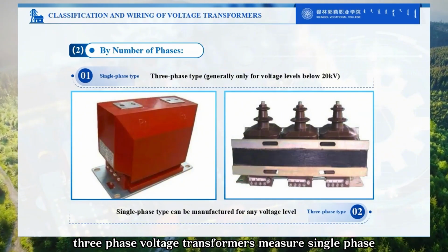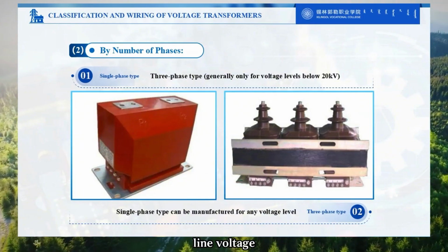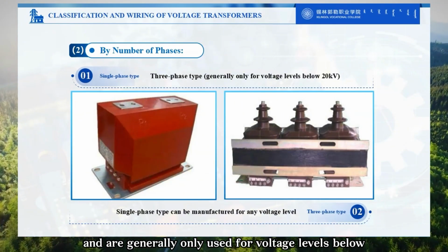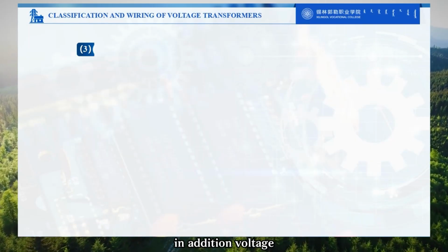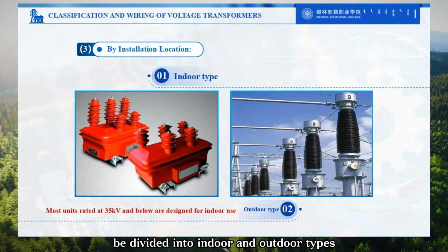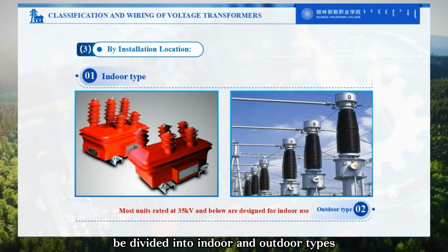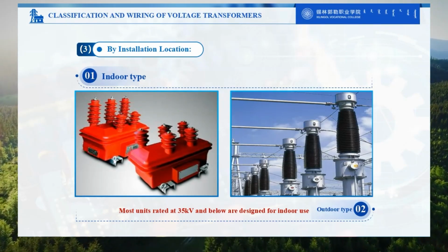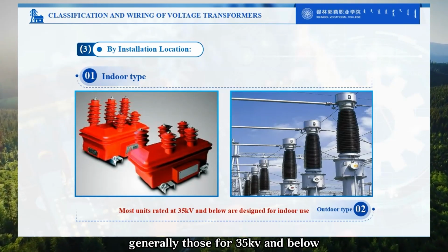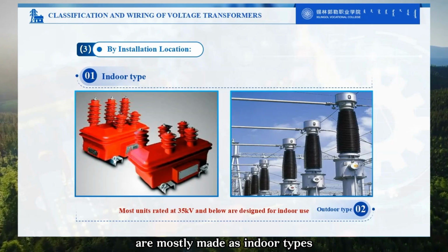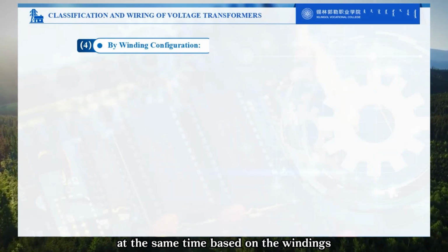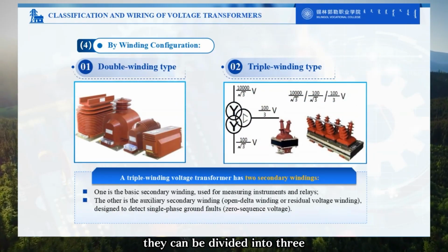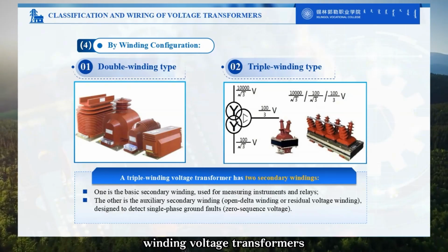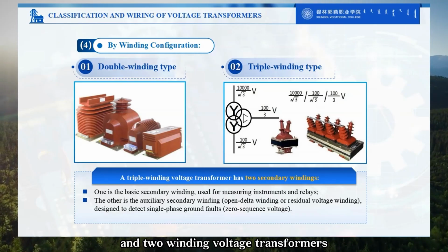Three-phase voltage transformers measure single-phase line voltage and are generally only used for voltage levels below 20 kV. In addition, voltage transformers can be divided into indoor and outdoor types based on the installation location. Generally, those for 35 kV and below are mostly made as indoor types. At the same time, based on the windings, they can be divided into three-winding voltage transformers and two-winding voltage transformers.